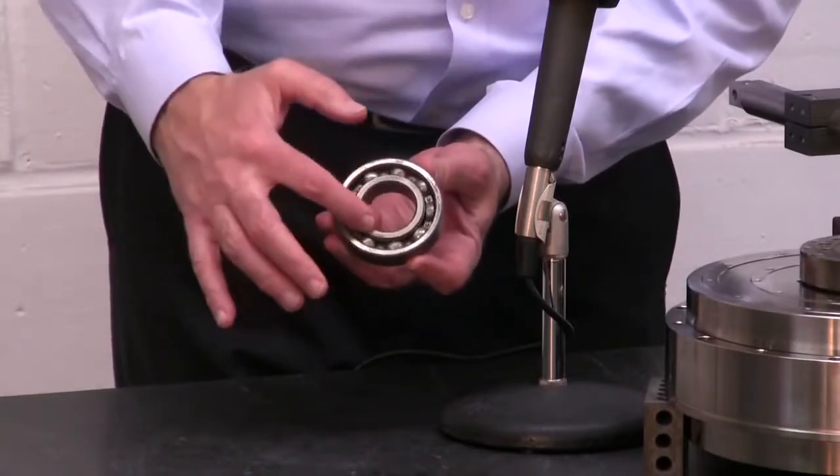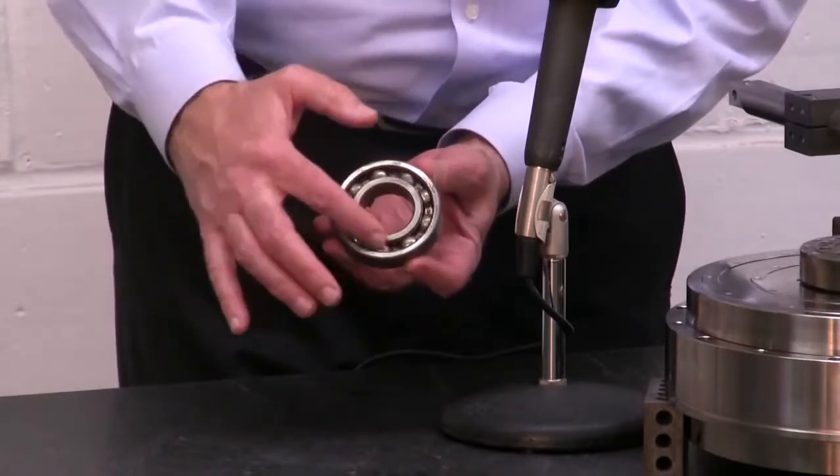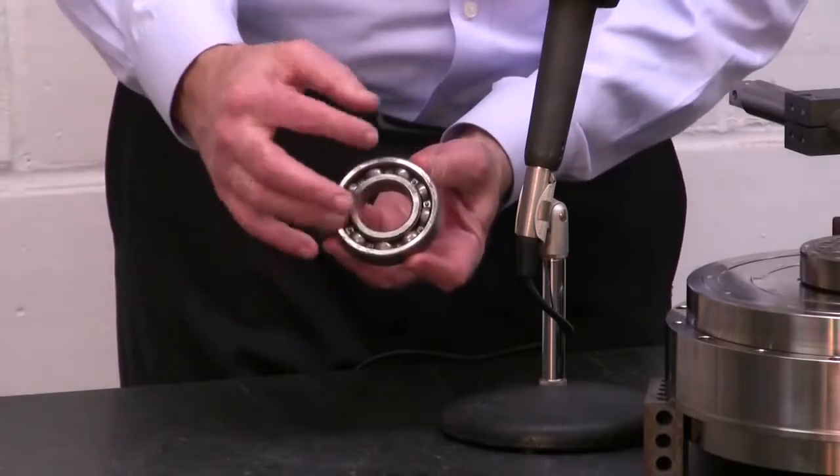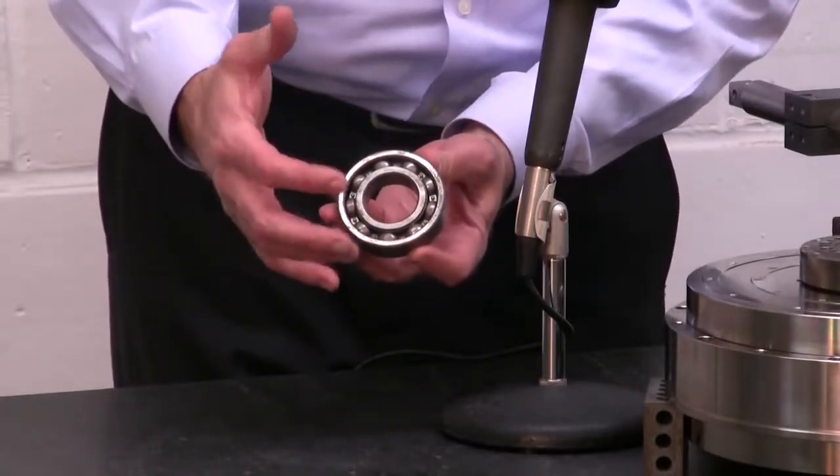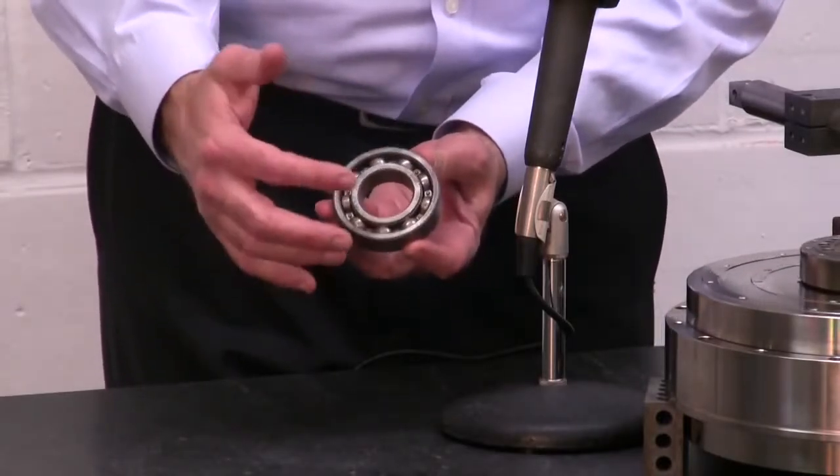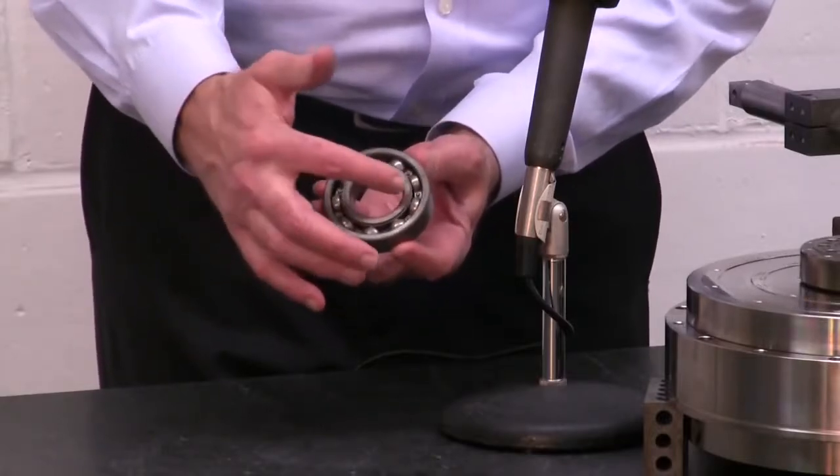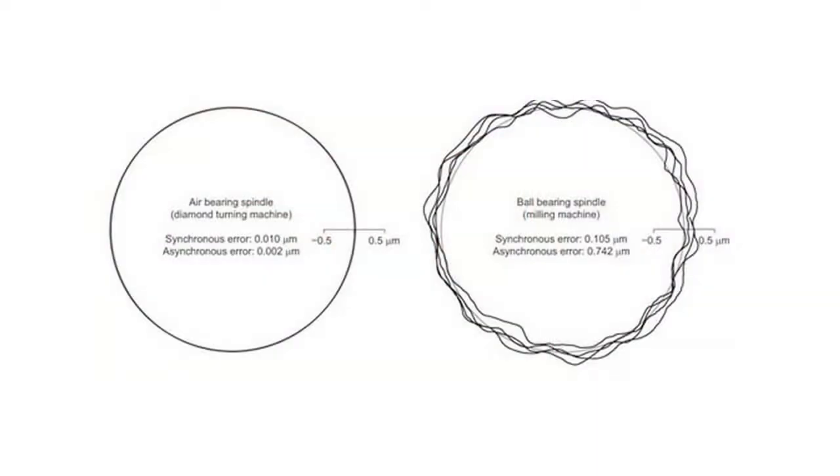The inner race is going to precess at a different speed than the balls. Because of this, all the little errors look like they're random. They're actually deterministic, but they result in what looks like a cloud around the rotation because of what appears to be random errors.